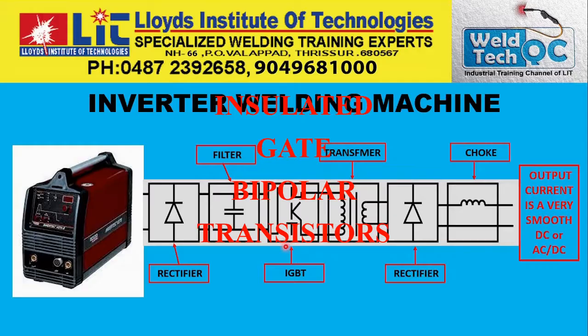It is actually a high-speed switching device which comes in various forms. The IGBT increases the frequency from a level of 50 or 60 Hz to a level of 20,000 Hz. IGBT receives only a DC signal. From here it comes to the IGBT, which is DC. It never receives an AC signal. It will not be activated.